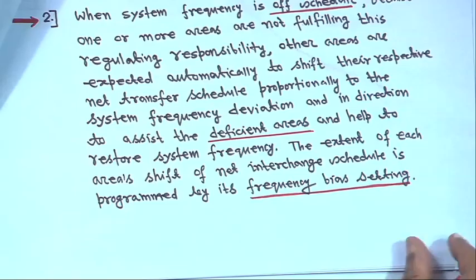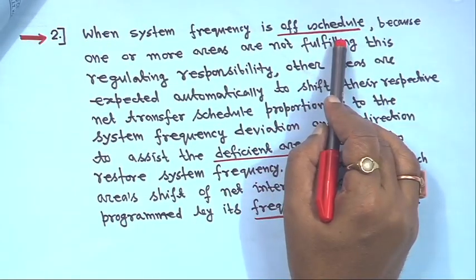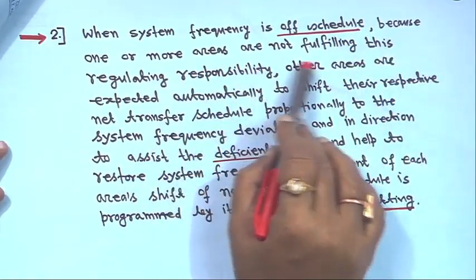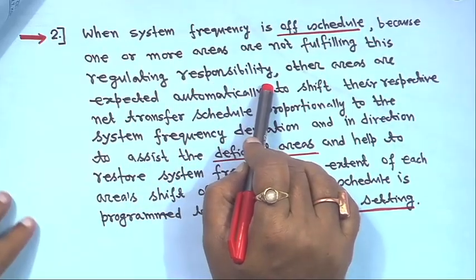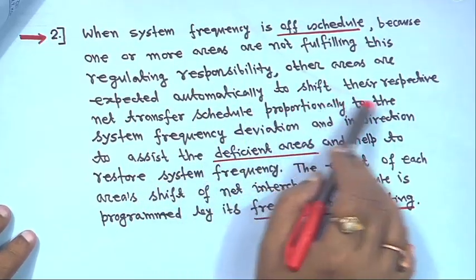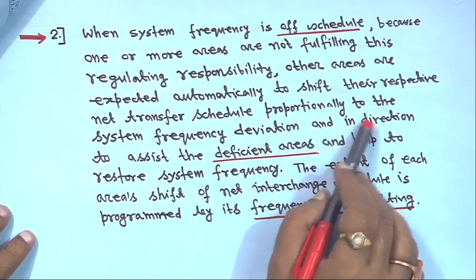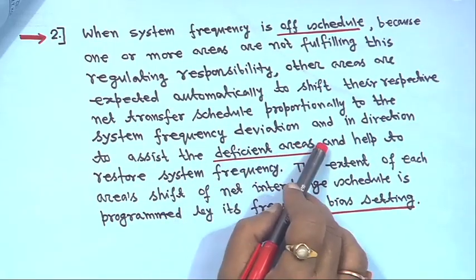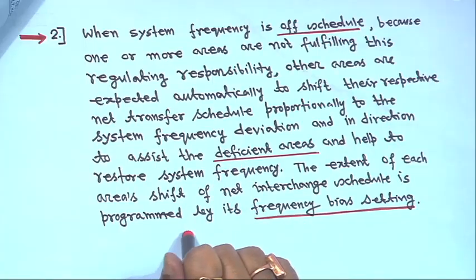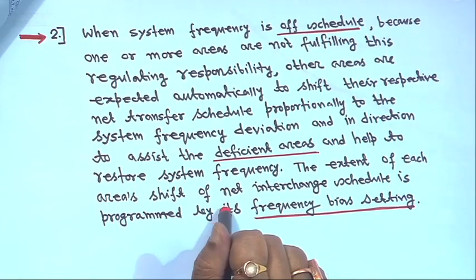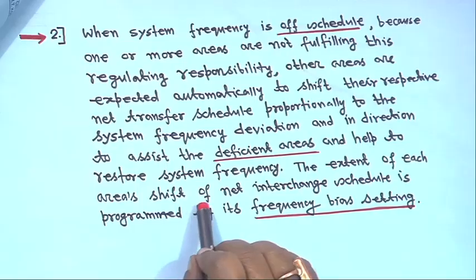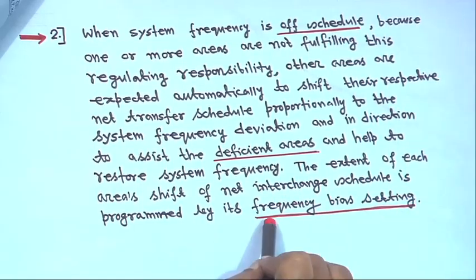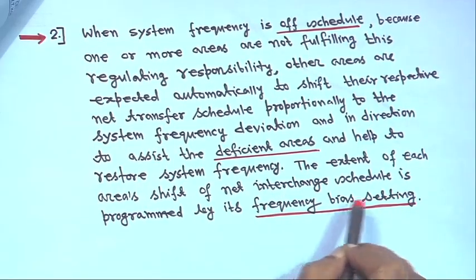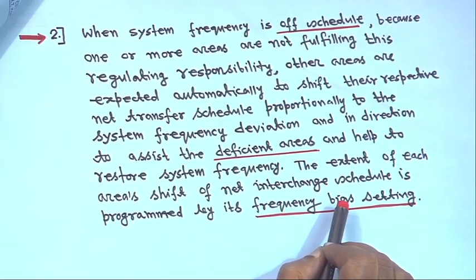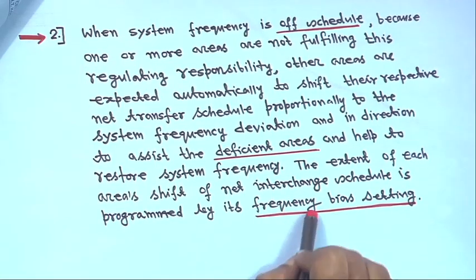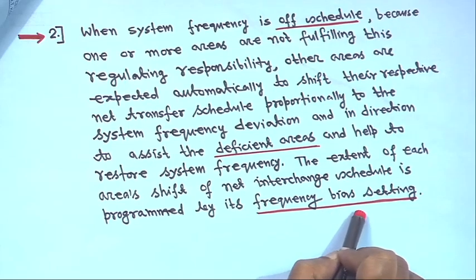The second one is when system frequency is off schedule, and it is not because of this area, but because one or more areas are not fulfilling their regulating responsibility. Other areas are expected automatically to shift their respective net transfer schedule proportionally to the system frequency deviation, and in a direction to assist the deficient areas and help to restore system frequency. The extent of each area's shift in net interchange schedule is programmed by its frequency bias setting. We will see that a little later. That is your B. You have seen D plus 1 upon R, the frequency response characteristic; that we call B. B is the frequency bias setting, right?